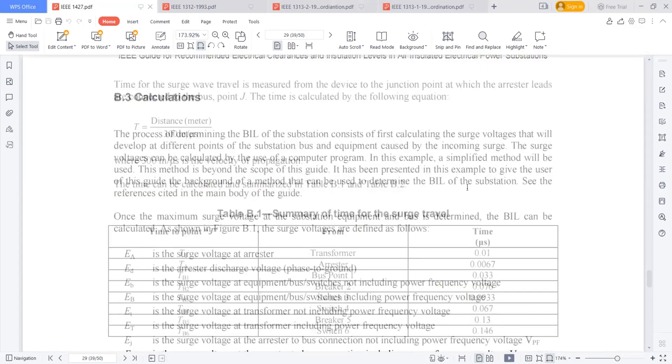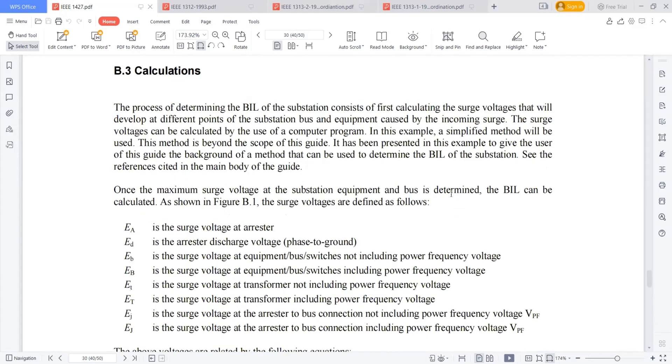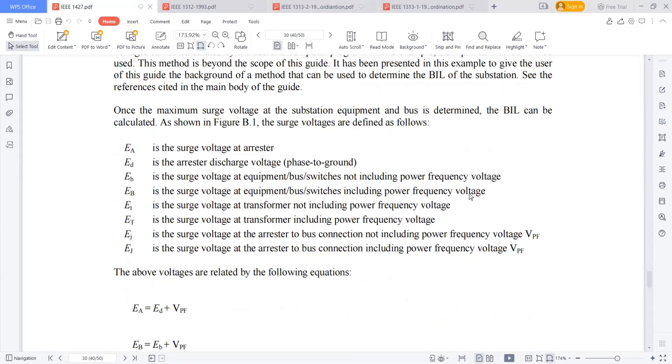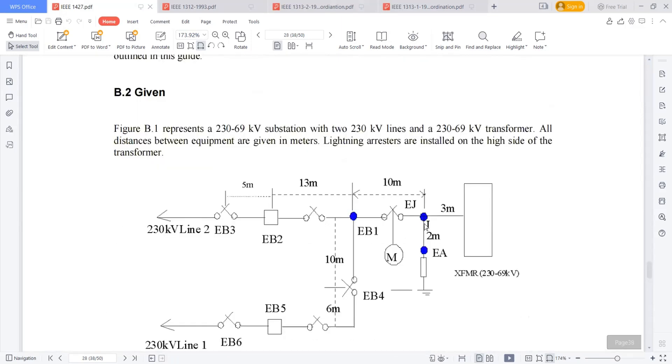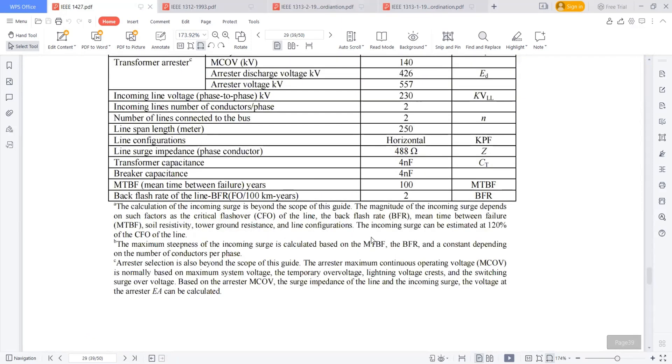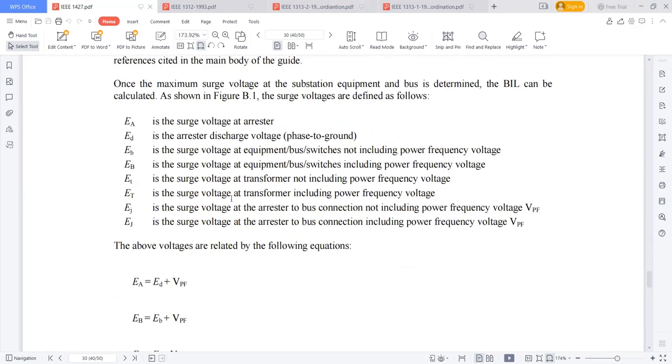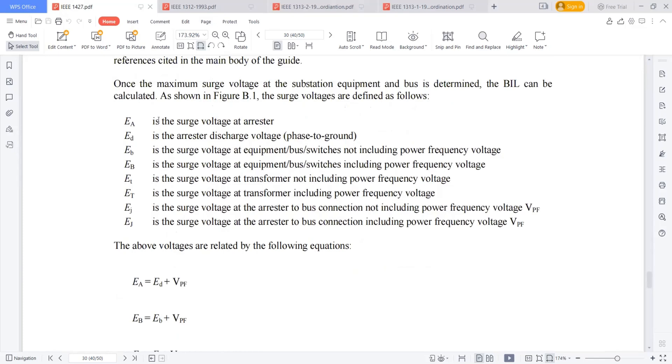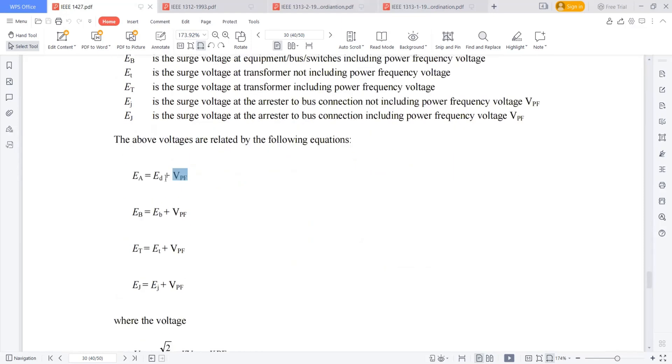After getting these inputs, then I am moving to the next step where I am calculating the voltage appearing at all these places when a surge occurred. I am calculating the surge voltages at all the places. This can be calculated by using these formulas. EA, which is the surge voltage at the arrestor, is equal to ED plus VPF. VPF is a power frequency voltage. And ED is the discharge voltage of the lightning arrestor.